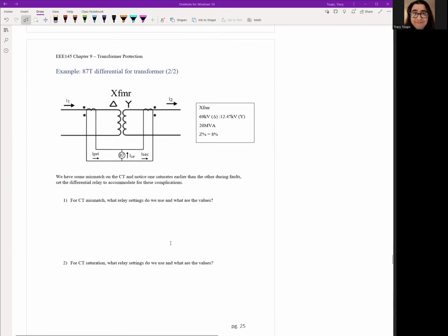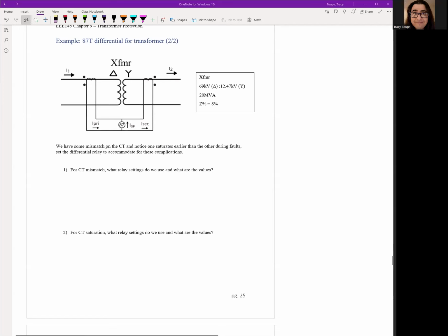inrush? Number 2 is we have some mismatch on the CT selection. We couldn't help it. And we notice that one saturates earlier than the other during faults. Set a differential relay to accommodate for these complications. So here, first off, what relay settings do we use to handle CT mismatch? Then what relay settings do we use for CT saturation and what's the value for that? So pretty simple. Just check out those two. We'll come back in about 15, 20 minutes to see what you've come up with and check your design. So see you guys in a little bit.